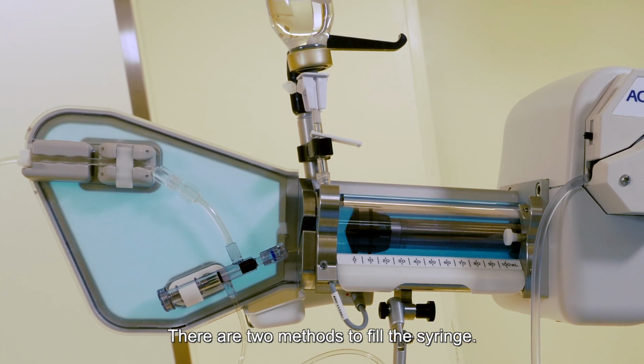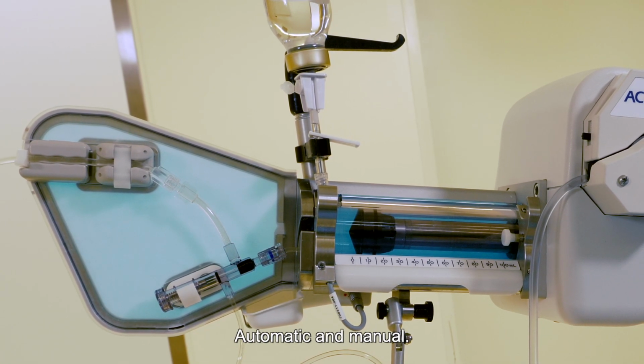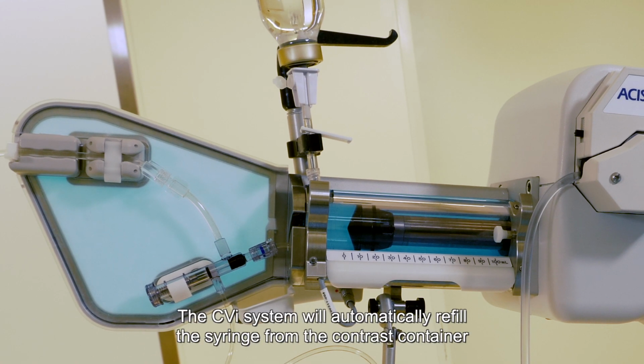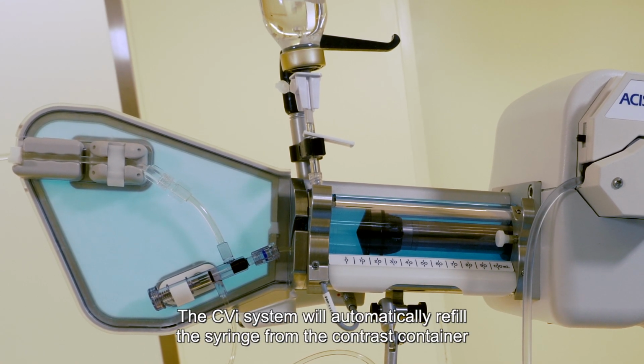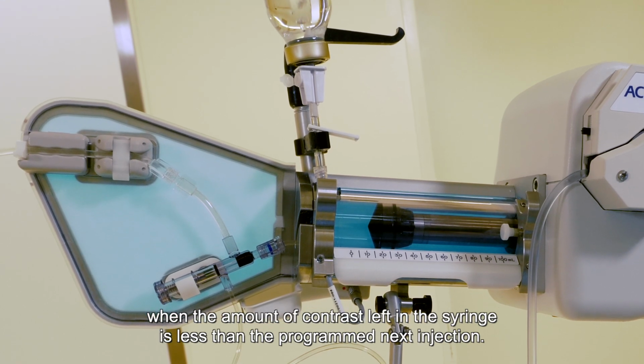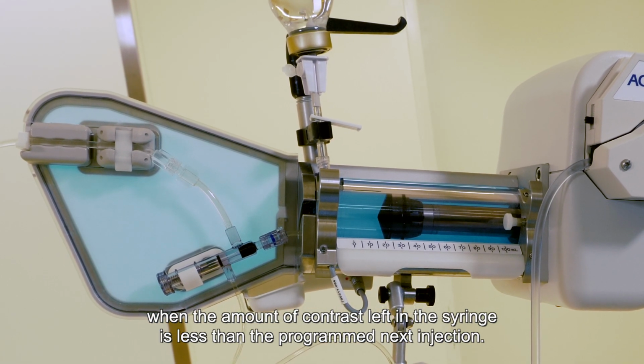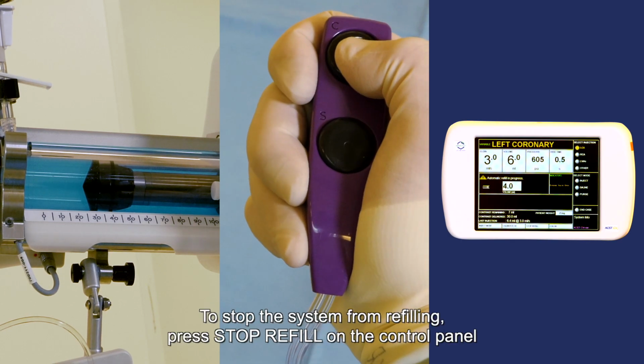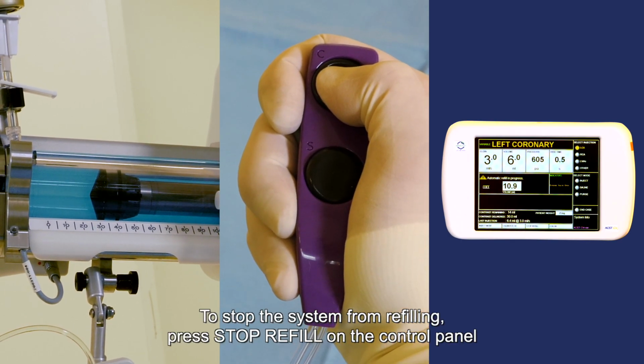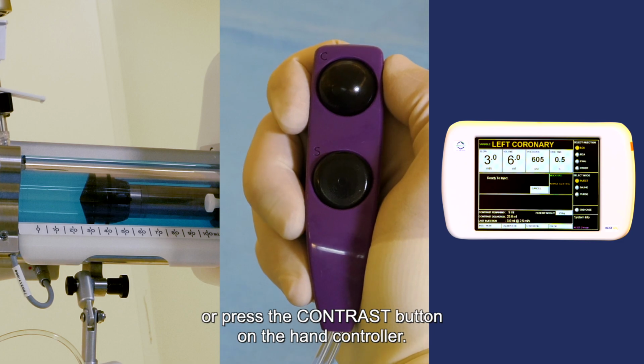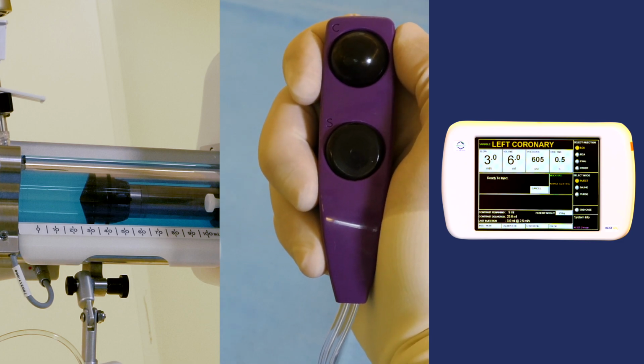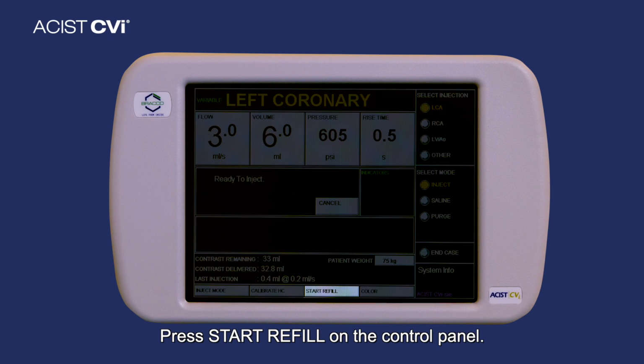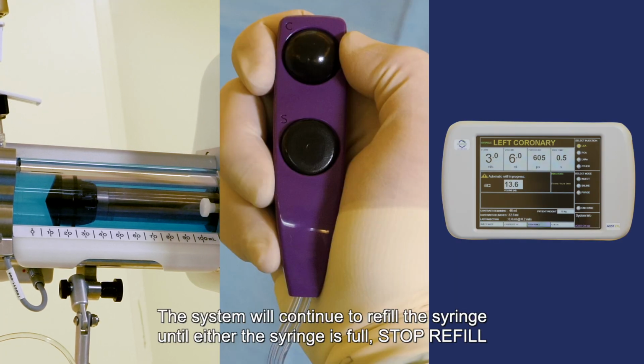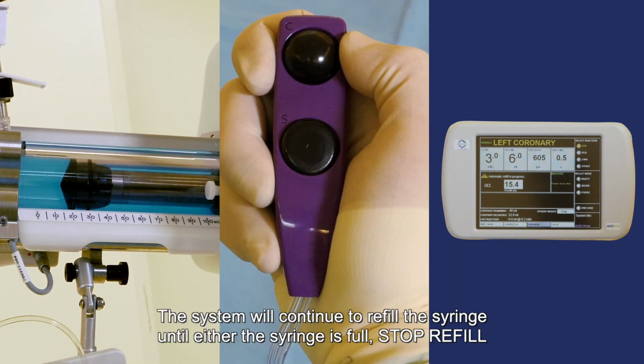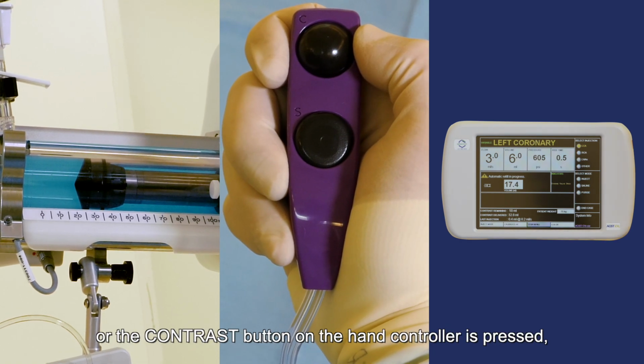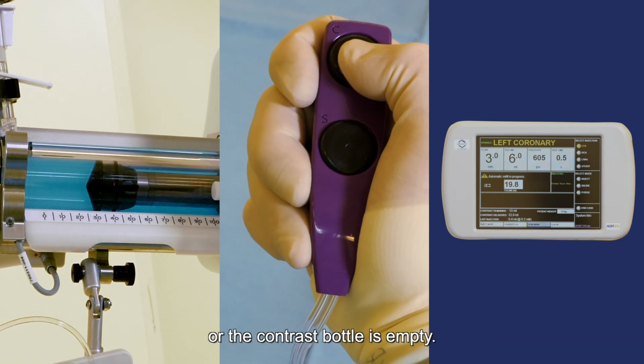There are 2 methods to fill the syringe: automatic and manual. The CVi system will automatically fill the syringe from the contrast container when the amount of contrast left in the syringe is less than the programmed next injection. To stop the system from refilling, press Stop Refill on the control panel or press the contrast button on the hand controller. Press Start Refill on the control panel. The system will continue to refill the syringe until either the syringe is full, Stop Refill or the contrast button on the hand controller is pressed, or the contrast bottle is empty.